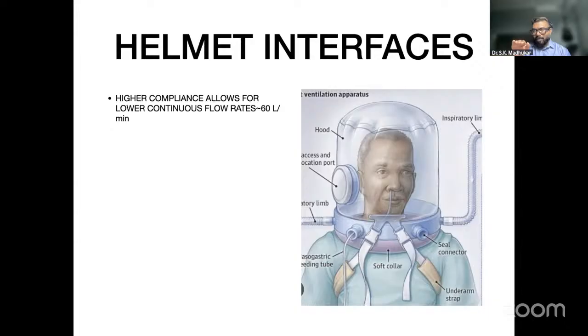Continuous airflow will help CO2 wash out. Whatever CO2 the patient is exhaling, that continuous airflow will sweep that CO2 out. Continuous airflow is very important for the trigger of the ventilator. As I told you, the trigger in this ventilator is spontaneous. When the patient starts inspiration, the patient takes some flow in. So there is a decrease in the continuous airflow, and that is sensed by the ventilator to trigger the breath. So continuous airflow is important.